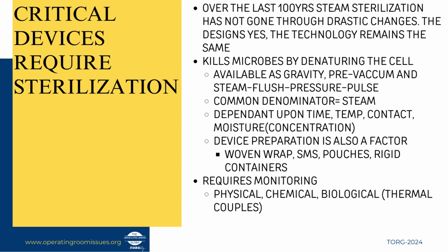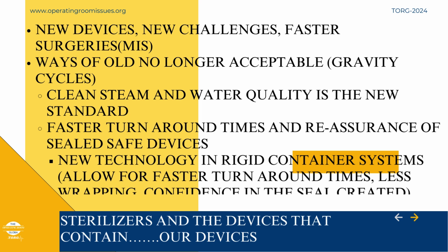Okay, new devices give us new challenges because of faster surgeries. This is the MIS surgeries. Okay, the ways of old are no longer acceptable. Gravity sterilization used to be very prevalent. Okay, now it's pre-vacuum because it's a faster cycle and it gets into the device a little bit better. Okay, clean steam and water quality is new to our standards. Okay, you can't clean with dirty water. Okay, you just can't. Okay, so water quality is extremely important when it comes to steam sterilization.